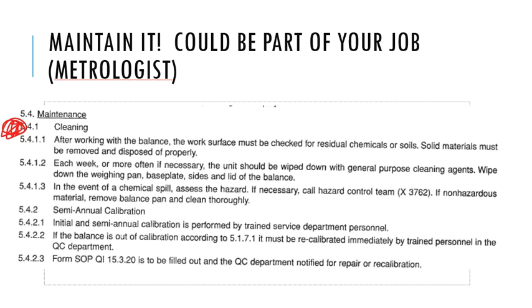So after you work with the balance, you want to check for all of those residual chemicals that might be left behind. If you do, sweep those out of there with like a little makeup brush, wipe them out with Kimwipes or paper towels. If they're larger spills, you need to tell someone about it, because then the balance has to be completely taken apart. We've got to do a complete deep clean from top to bottom with those.